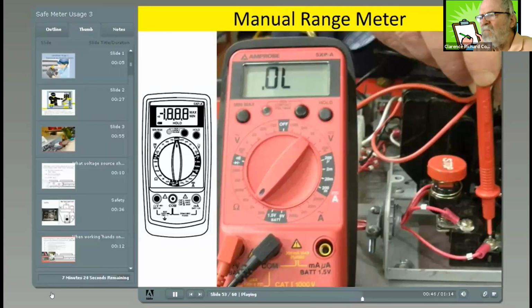Important. Notice that the probe is being held at the end of the probe. In this slide, we are just measuring resistance with power off. The technician is careful not to be part of the circuit by directing the probe tip from as far away as possible. Many times, beginner troubleshooters slide their fingers down as far as the finger guards. This is unnecessary and should be avoided. The troubleshooter should clip one lead to ground and probe with one hand.